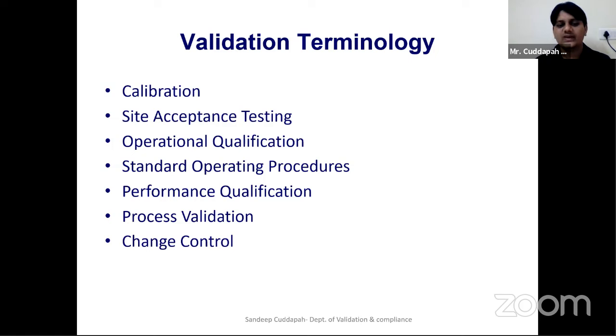Then you have process validation. Once your equipment is qualified, you have to use it for some process. So the first thing to consider is process validation. In that case, you will fine tune or verify the equipment's operating set parameters, whatever you defined during performance, to see if they are suitable for your process. Suppose you have to do some distillation. You have done performance qualification for a small heating bath at 50 degrees, but your process is distillation and you need 100 degrees. That is what you verify in process validation: whether the equipment is suitable for your process or not.